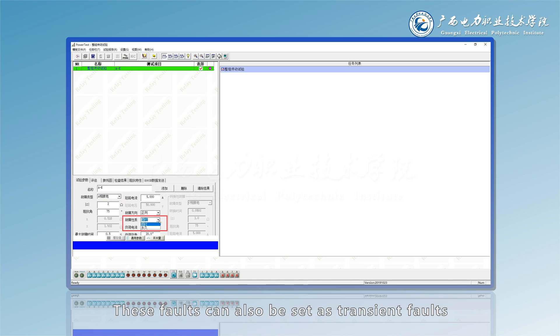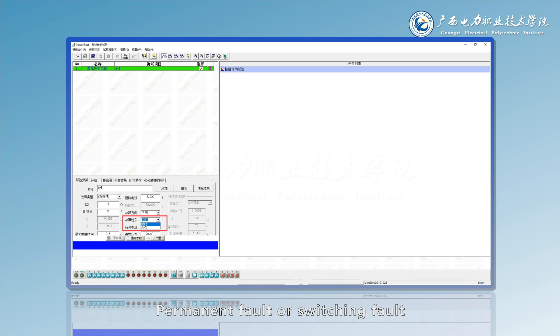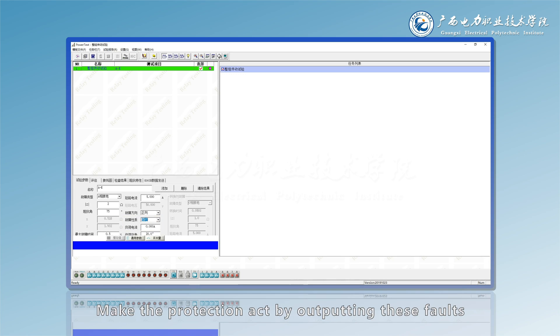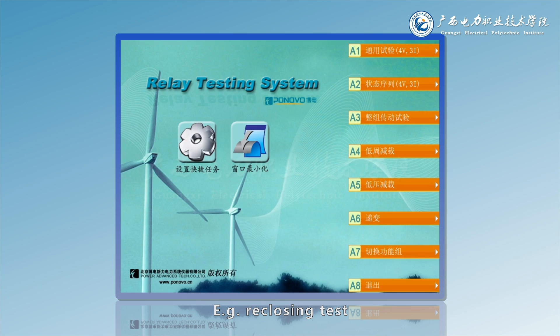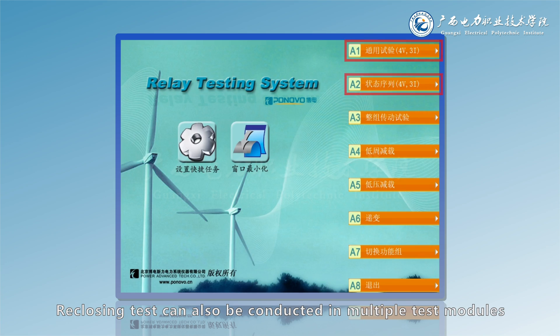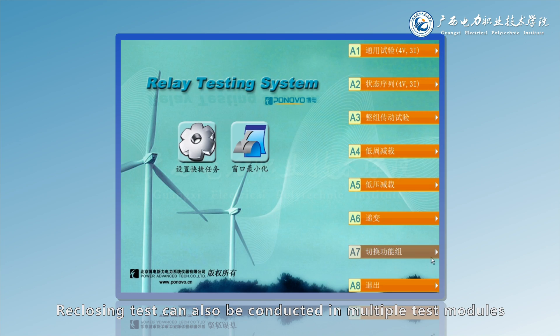These faults can also be set as transient faults, permanent fault or switching fault to make the protection act. By outputting these faults, circuit breaker trips. For example, reclosing test can also be conducted in multiple test modules.